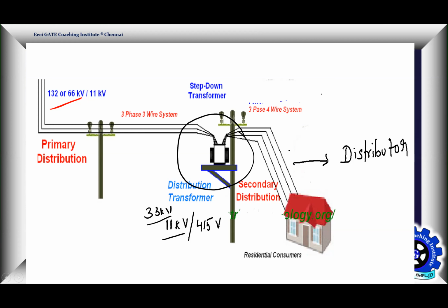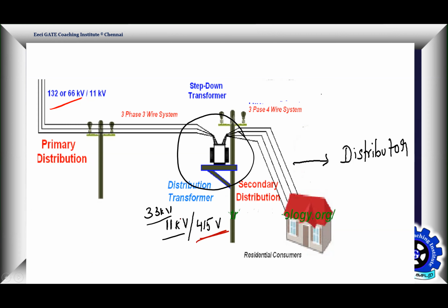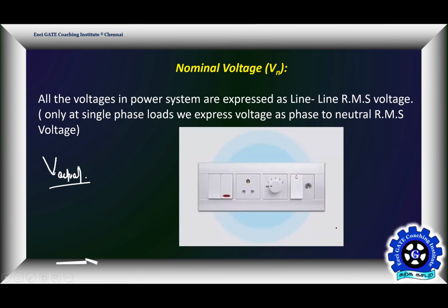Now if you look back at the primary side of this transformer, on the secondary side you are supposed to get 415 volts. Now tell me, what is the primary voltage? It is 11 kV or 33 kV - this is called the nominal voltage at the primary side of the transformer. If you actually go and measure the voltage, it may not be exactly 11 kV - it may be slightly higher or lower. So nominal voltage is the voltage that we are supposed to get at any point in the power system network, but there will be a slight difference between the nominal voltage at that point and the actual voltage at that point.